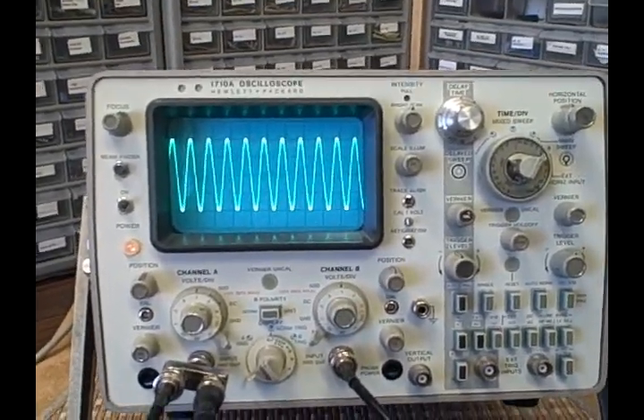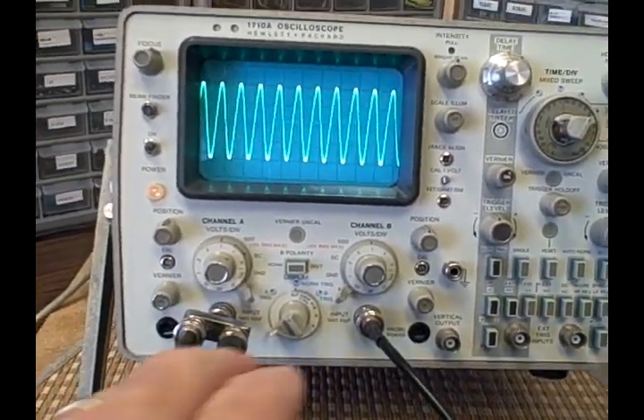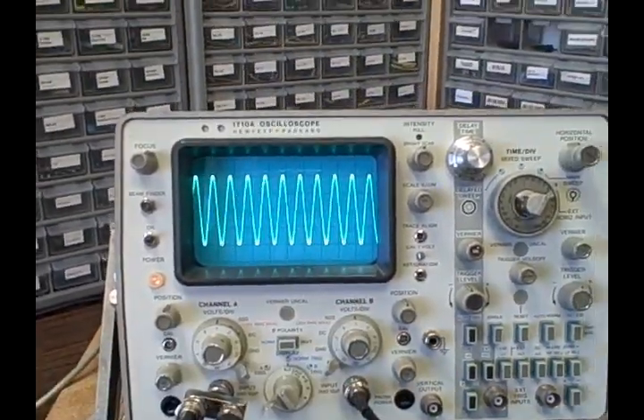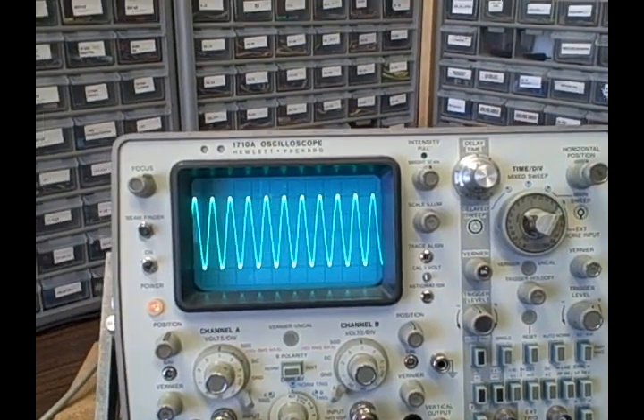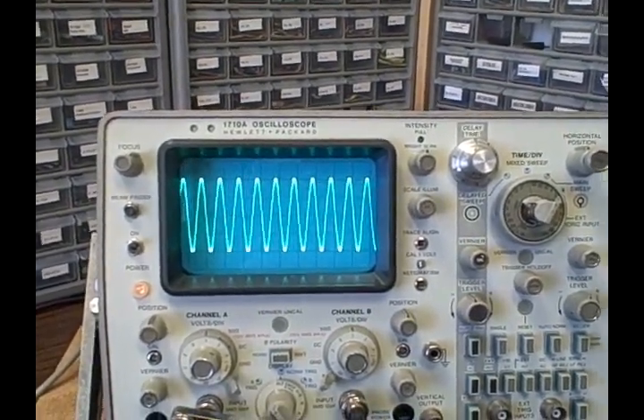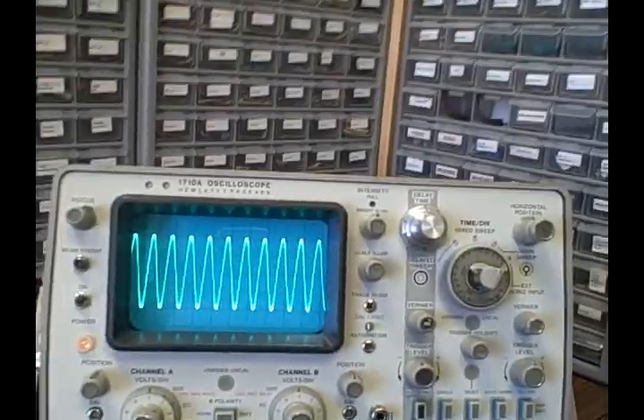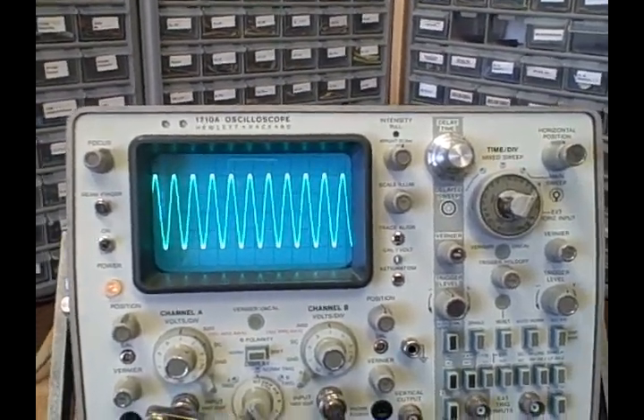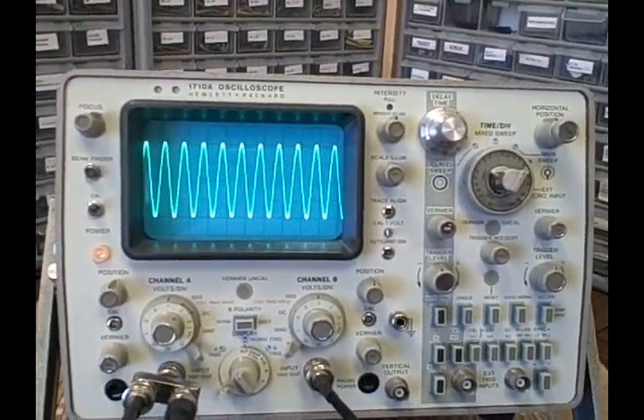As you can see, we have one signal on there, but we show that we're in alternating mode. We have two signals on there, but you only see one. That's because they're tracking each other very closely, which they should if they're in good calibration.